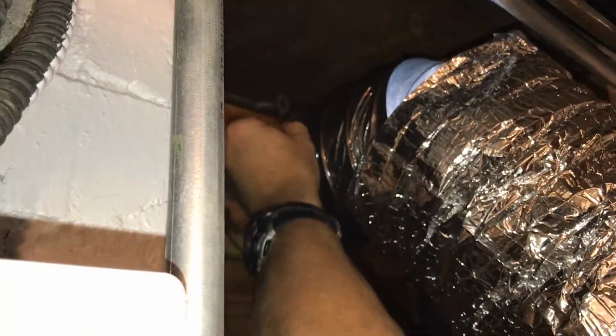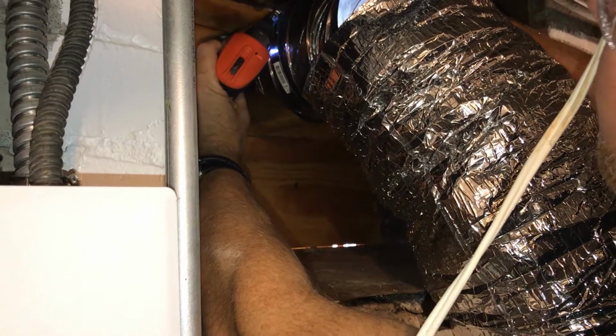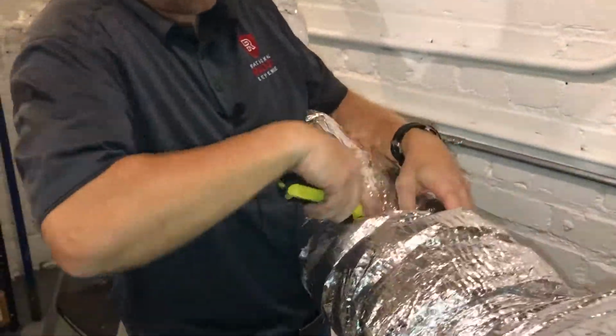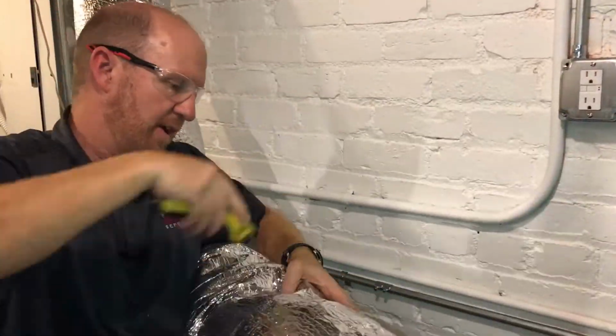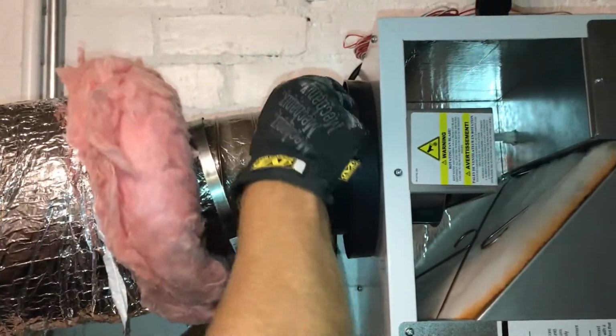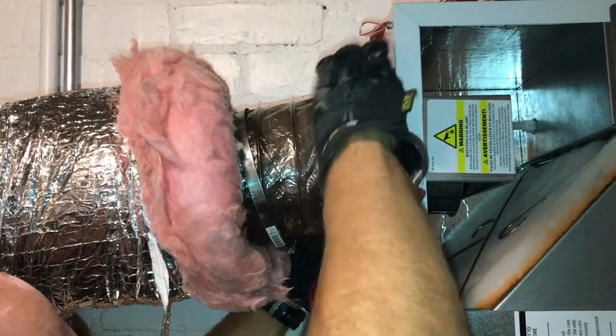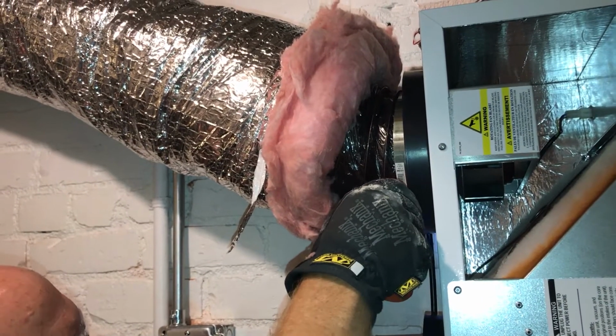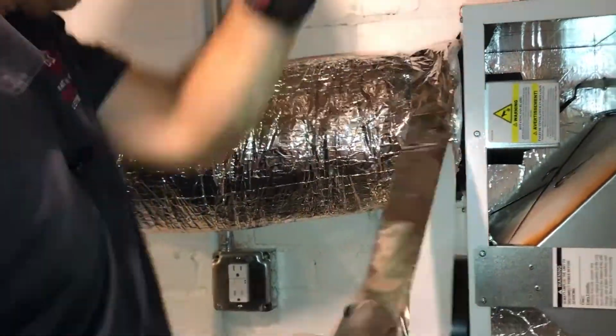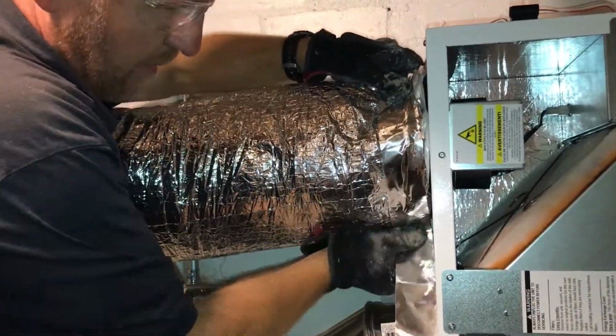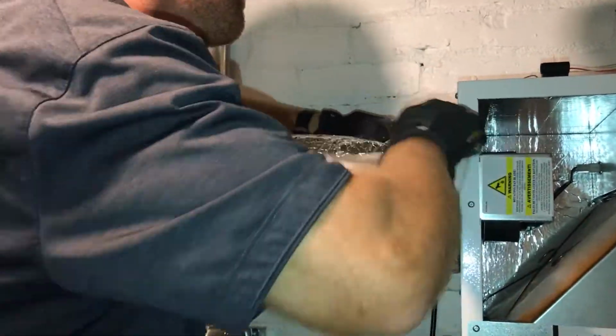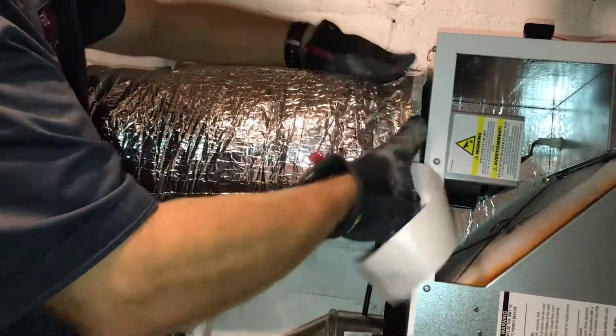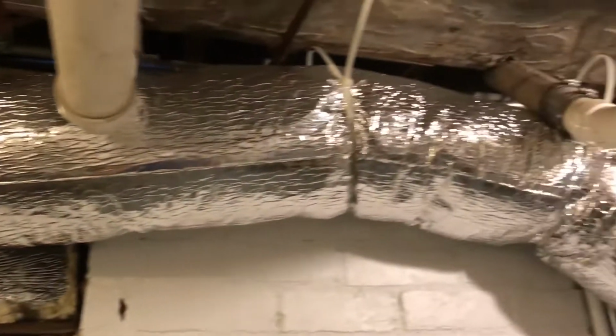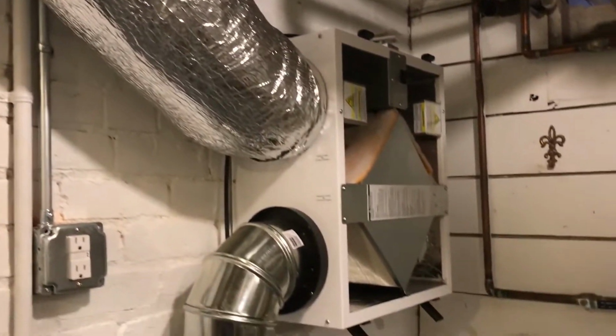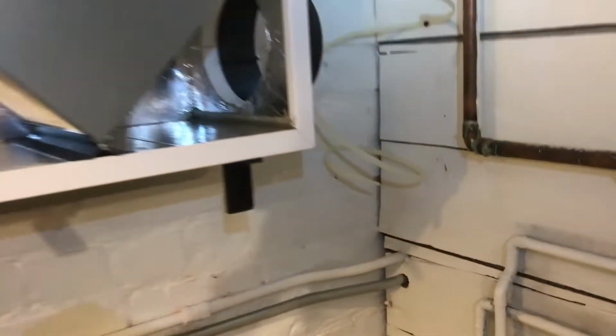Here we're connecting our fresh air intake ductwork to that vent that we're coming through the coal chute. And so I'm using the clamp to clamp the ductwork to that vent, and then I'm basically cutting our ductwork to size, clipping off the wires and connecting it to the vent connector on the ERV. We've insulated the back side of that plywood that we're using for our ventilation intake, and we've completed our complete intake run. Now we're going to focus in on installing the exhaust run.